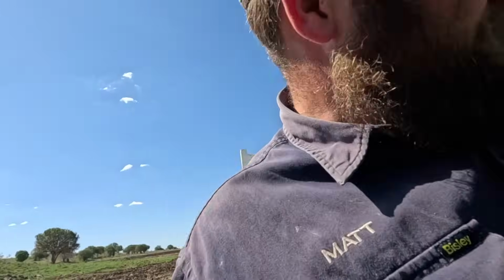Righto, guys. That's a good look, isn't it? Yeah, found that it was low on gas a bit, but it's just a hot old day, and what happens is I just can't get the pressure down on the high side.